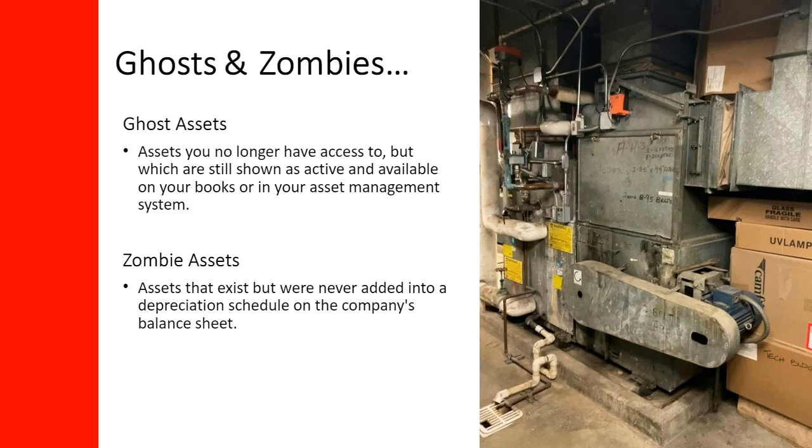They're chasing that information. And the reason I leave this up where it says the zombie assets is, are you sure that those assets were added to your database? Who's maintaining that? Another example is I talked to a hospital, 8 stories, 800,000 square feet. Their outside vendor won't get on a ladder. When they did the FCA, they missed 50 fan coil units that are up in the ceiling grid. They didn't even get up on the roof.